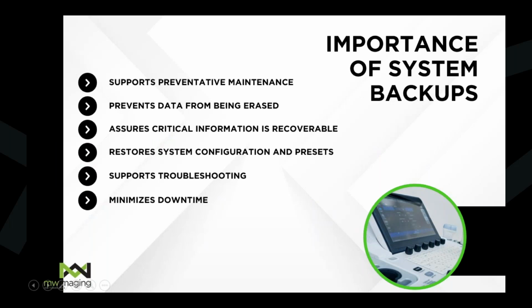We also use it in supporting troubleshooting. I don't know how many times I've gotten a call via tech support or had to go on a service call where one of the users, the sonographers, have been messing around with some of the settings on the system, and now they have image quality issues, or they can't figure out why it's doing a workflow a certain way. So if I have a good backup, I can always say, hey, well, this backup was from 6 months ago. I'm going to throw this on there, see what it does, see if it fixes your issue, especially if I think it's a user setting that the sonographer may have changed.